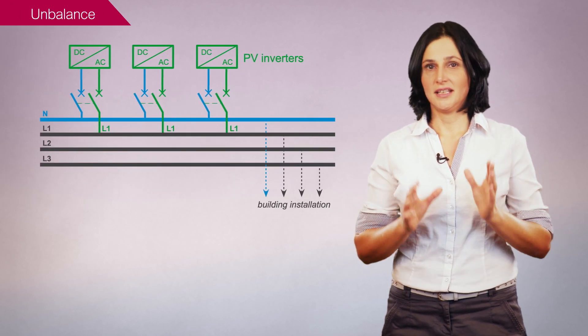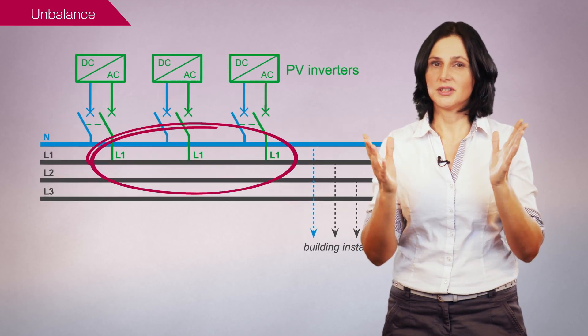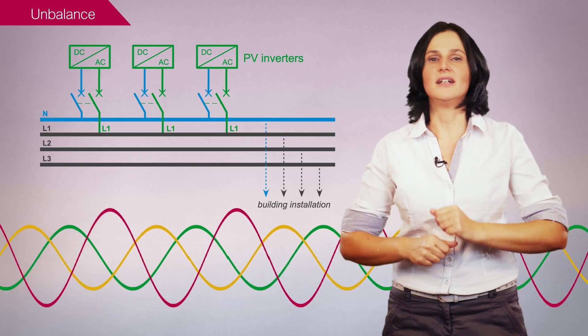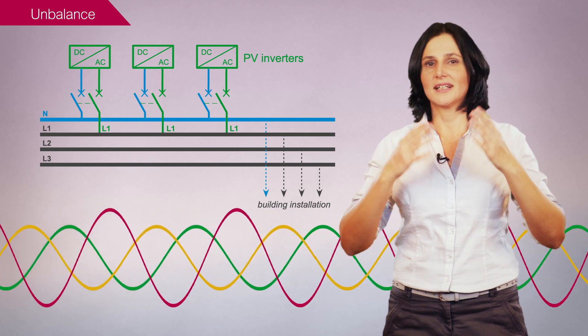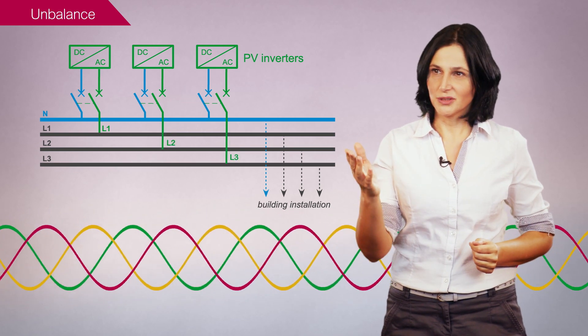A third potential disturbance is unbalance. Unbalance can be generated if single-phase photovoltaic inverters are connected to a three-phase electrical installation. To avoid unbalance, it is recommended to connect the photovoltaic inverters evenly across the three phases as shown here.